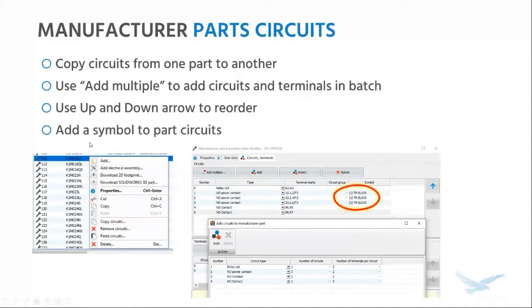If you're going to be adding a bunch of circuits of different kinds, the Add Multiple tool is a huge time saver. This allows you to add different types of circuits, control the number of circuits of each type, and the number of terminals per circuit. There's also the up and down arrow to reorder circuits. When matching symbol circuits against part circuits, SolidWorks Electrical looks at the circuit types and the order, so setting them up correctly now could save you time during design work. You also have the option to add a symbol to the part circuit — if you find yourself using the same symbol for all your relay coils or three-pole normally open power contacts, just link a default to the part circuit.